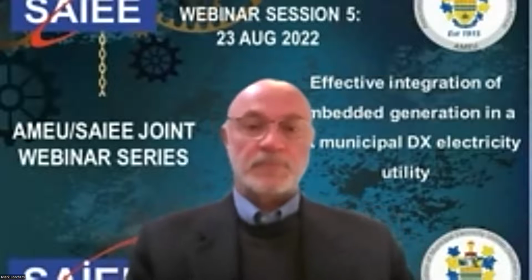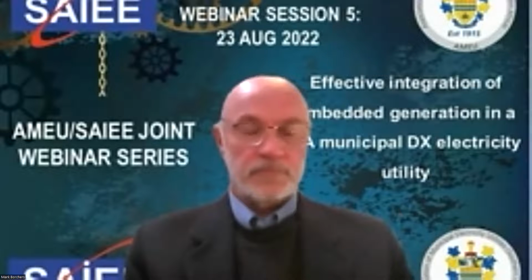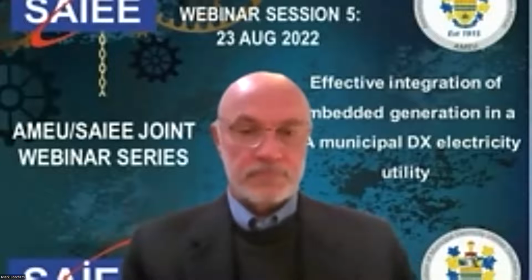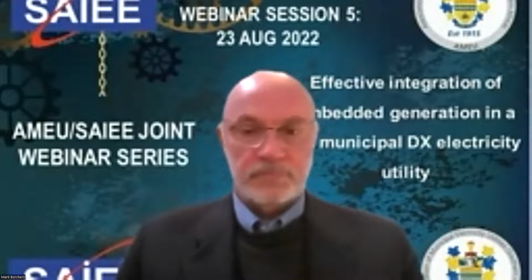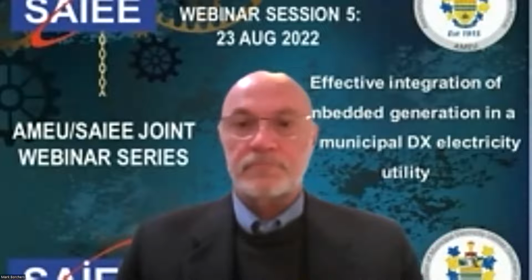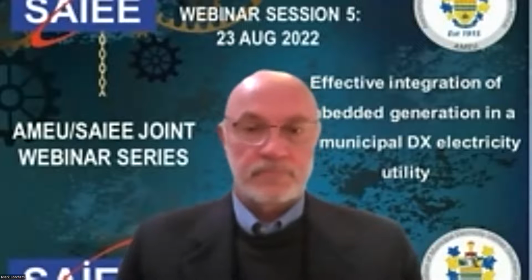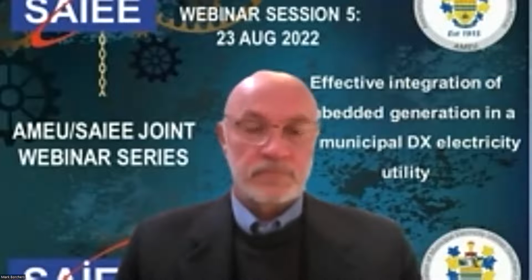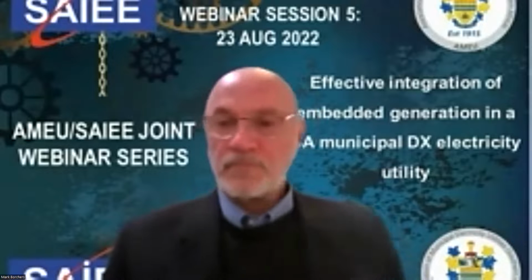Because currently what we are doing is, you'll find that, for example, a substation does have capacity, but you find that the loading is not so much, all right? And then it becomes an issue where the IPP wants to connect on that substation and finds that it's actually a primary substation. What I mean is that this is an Ekurhuleni substation where we get power directly from Eskom. So if the IPP injects more power there than the loading on that substation, the remainder will flow back to Eskom, which then becomes an issue.